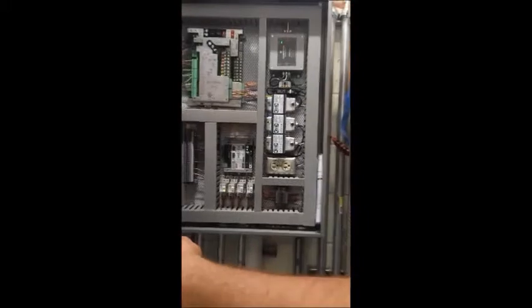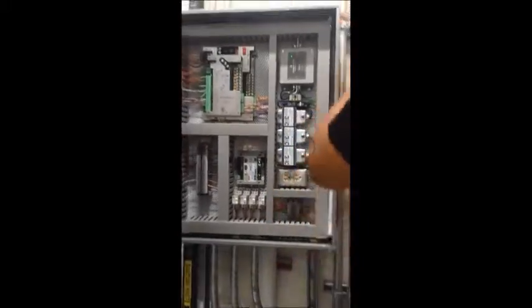Control. Do we check the chemicals for the closed loop? Once a month. Once a month will be the building. And then obviously this is the ALC controller for this plant. It relates your pumps, you start the drives, the outputs.